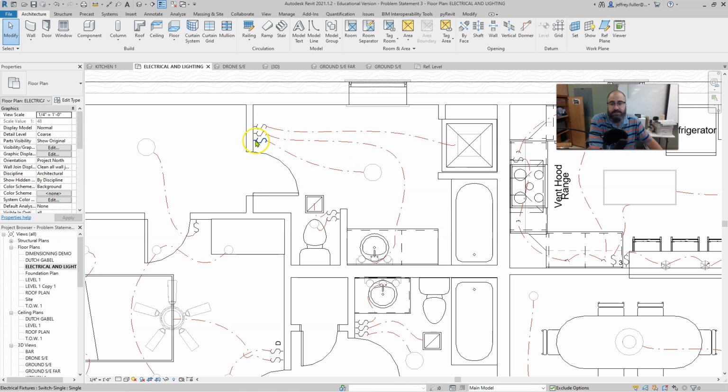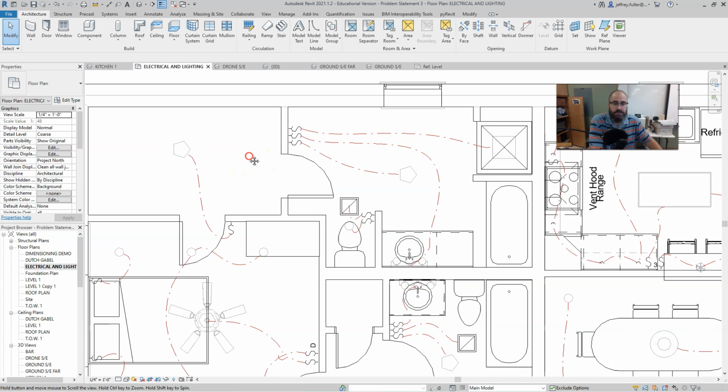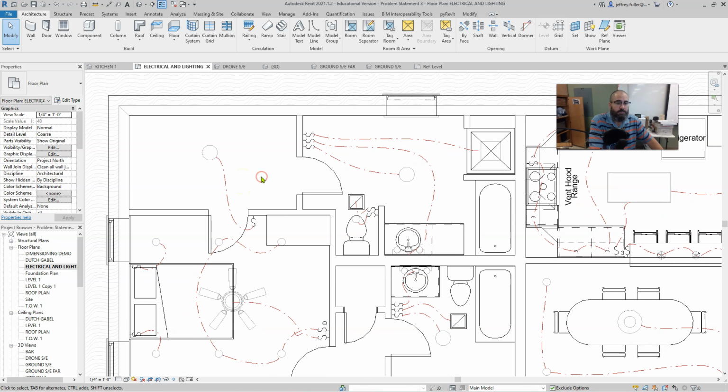And the main light is the one that I locate closest to the door opening. And that's the way you want to do that. So always the main light gets closest to the door opening. It will be the first light switch that they would switch on in order to see where they're going. And speaking of positioning of switches in that manner, the light switches always go to the side that the door opens. Right here you see the opening where I come in, the door swings to the right, but the switches are going to be on the left. And it will be just the opposite for doors that swing to the left. Then your switches would need to be on the right.